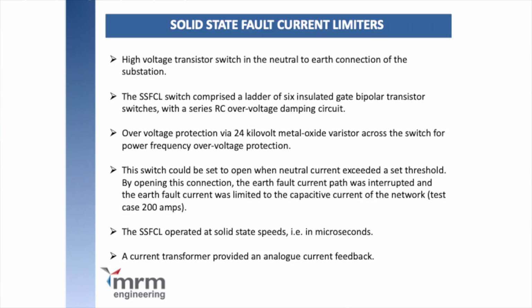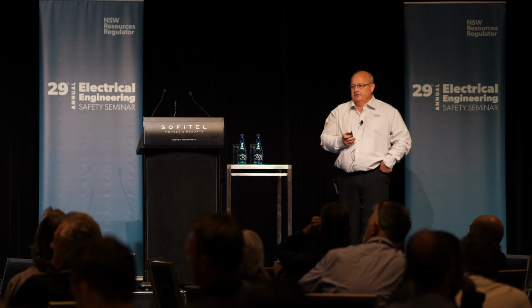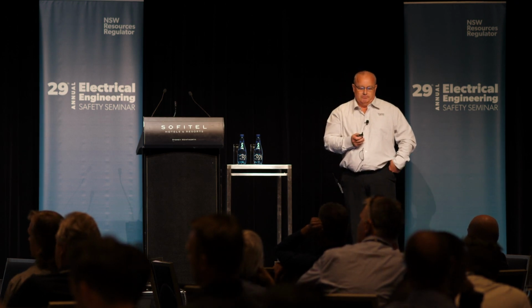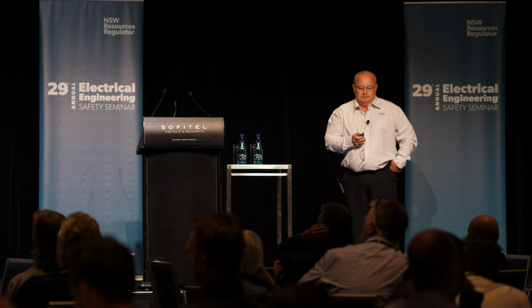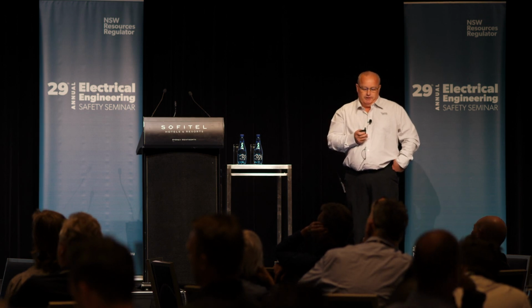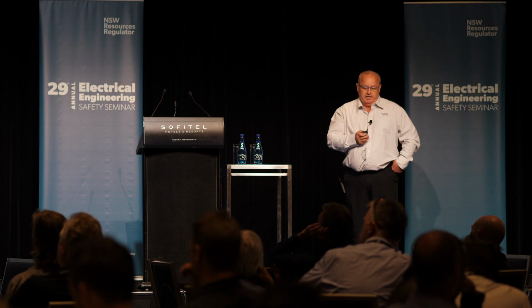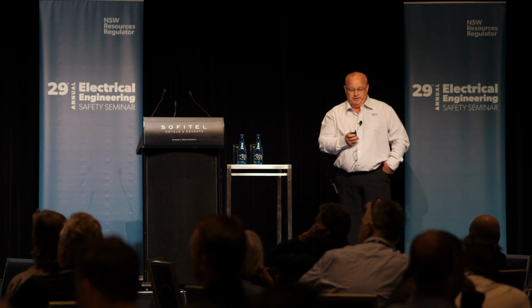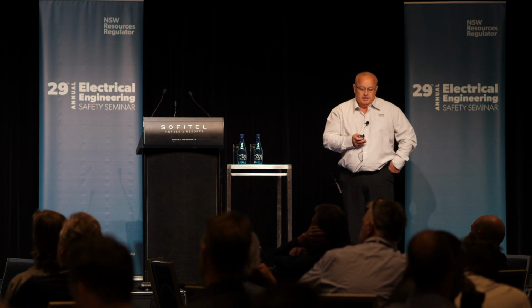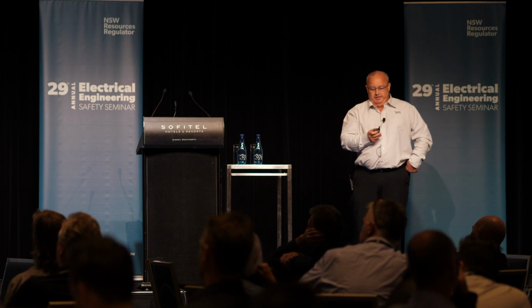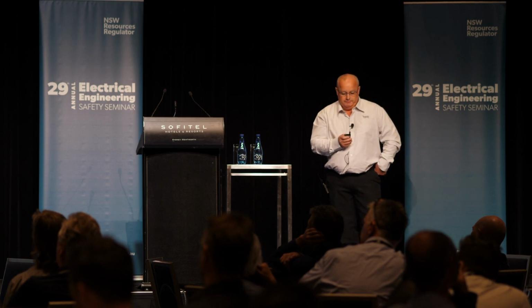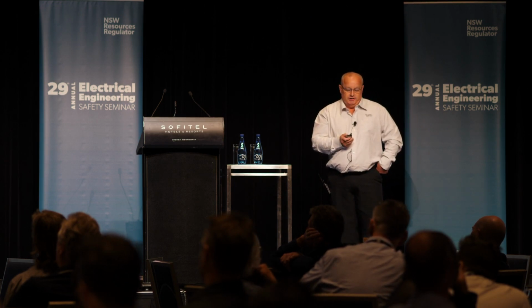So the second type is the solid state fault current limiter. It's basically a high voltage switch inserted in the line from the ground to neutral. So it's a group of IGBTs, which like this one here, the one we looked at, was 6 insulated IGBT control switches with an RC network, provided over voltage protection via a metal-oxide varistor. The system could be set to trip when the neutral exceeds the threshold. The solid state operates in microseconds, so we'll have a look at that in a minute as far as the speed of the operation. And the current transformer provides an analog feedback into the network, which then operates into your tripping circuits or your circuit breakers.